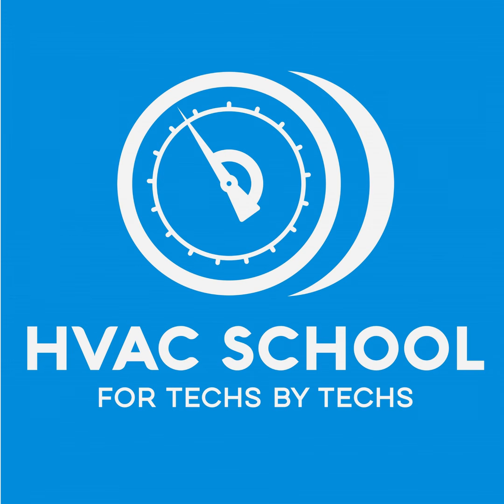To answer your question, though, I've always told people to think of a VRV heat pump system as a hydronic system. It's no different than having a central plant, which is our outdoor units, providing hot or cold water to all of our indoor terminal units. You could have a heat pump, which is much like a 2-pipe hydronic system. So everything needs to be all in heating, and then in summer mode, you would switch over to cooling. The difference is with a heat pump, you could switch back and forth as quickly as 15 minutes.